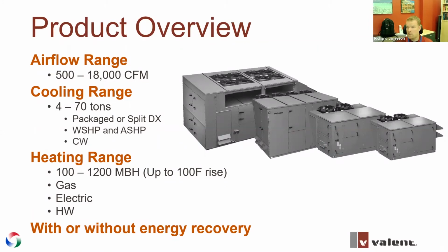As far as cooling capabilities, Package DX is the majority of what we do. We can also do a split system, an indoor unit paired up with a remote condenser, keeping the compressors inside. We can do a water source heat pump or an air source heat pump and chilled water cooling. On the heating side, gas heating is our most typical option, and we can go up to 1200 MBH on that, but we can also do electric or hot water.